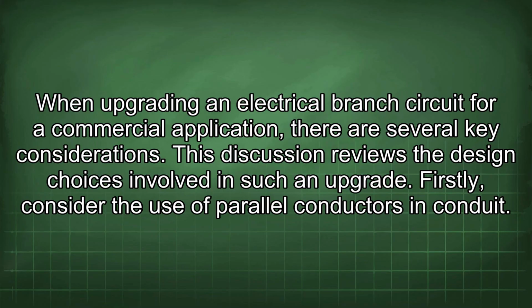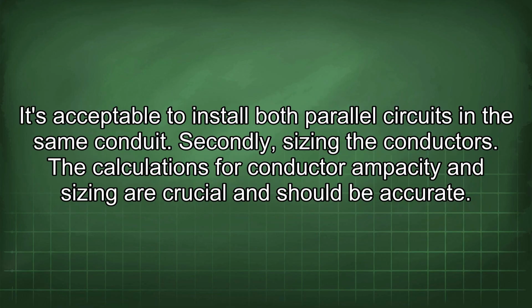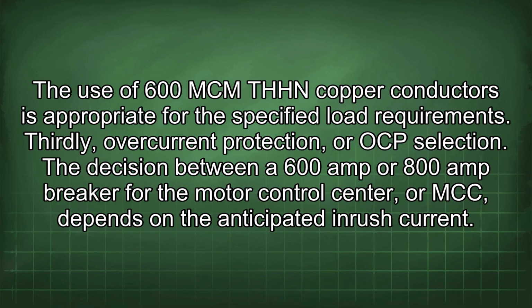When upgrading an electrical branch circuit for a commercial application, there are several key considerations. This discussion reviews the design choices involved in such an upgrade. Firstly, consider the use of parallel conductors in conduit. It's acceptable to install both parallel circuits in the same conduit. Secondly, sizing the conductors. The calculations for conductor ampacity and sizing are crucial and should be accurate. The use of 600 MCM THHN copper conductors is appropriate for the specified load requirements.